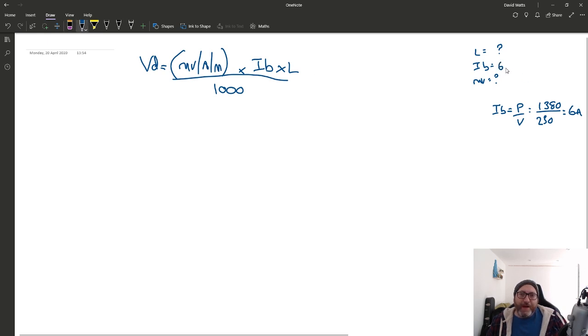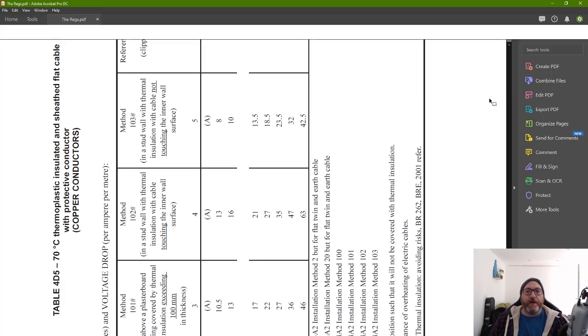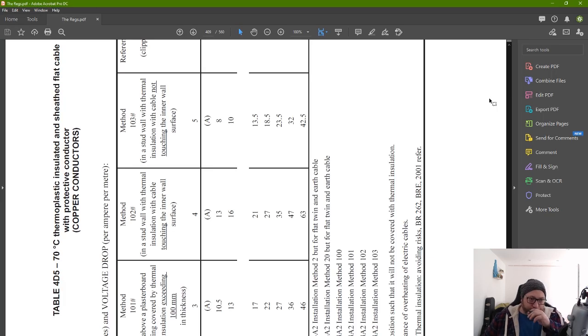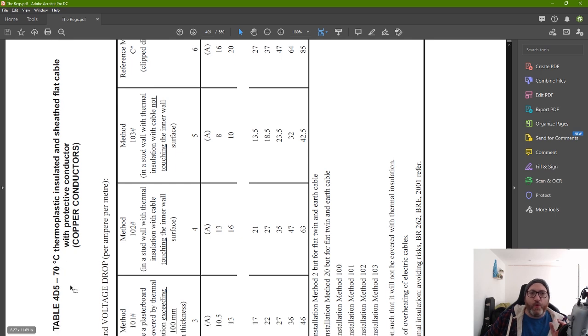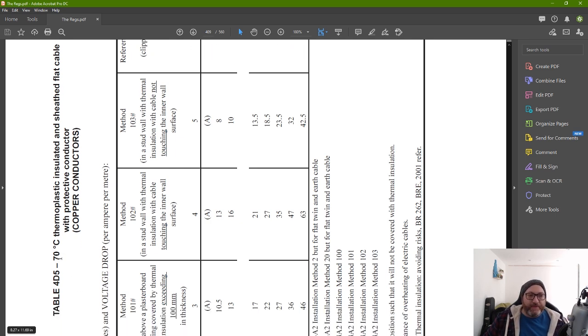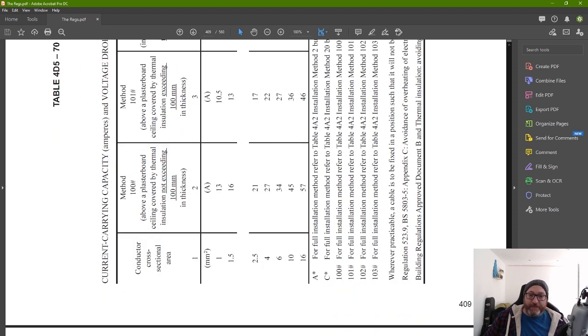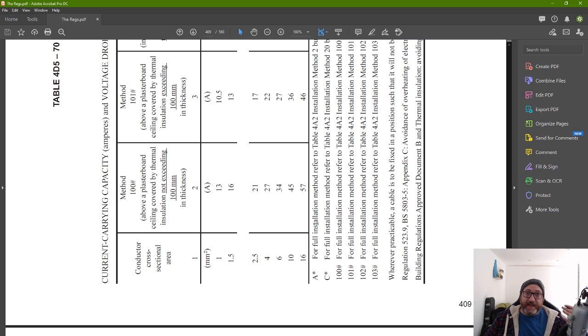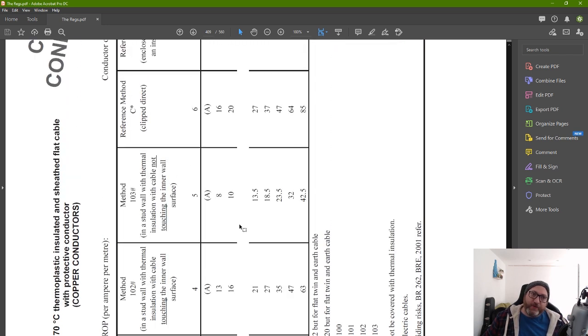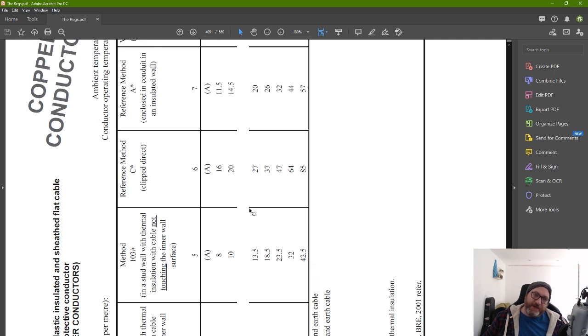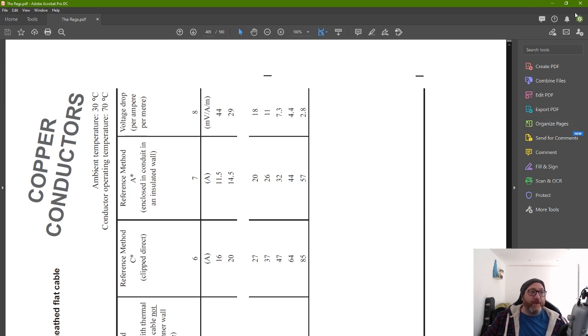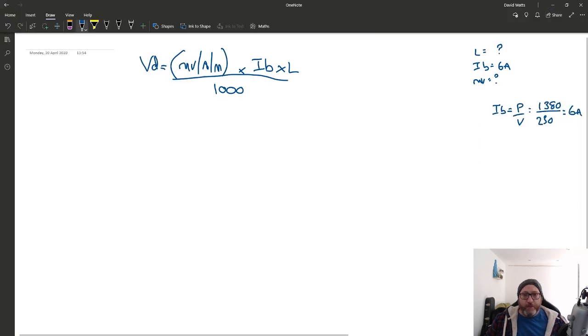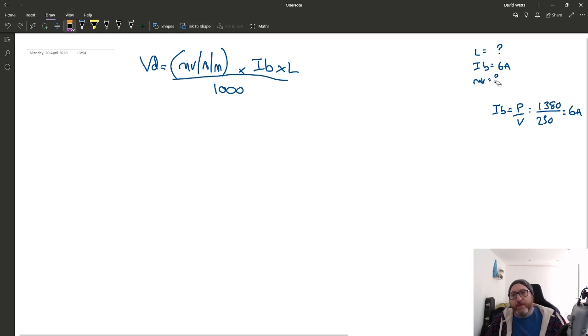To get the millivolt per amp per meter value here, we need to go to BS7671. And we need to go, because it says it's a flat profile cable, table 4D5. Table 4D5, this is page 409, just in case, this is the 18th edition. So, 1.5mm flat profile cable, and you can see the volt drop column, I know this is sideways, the volt drop per amp per meter column is 29. So, the value for volt drop in millivolts is 29. And we can move forward with that.